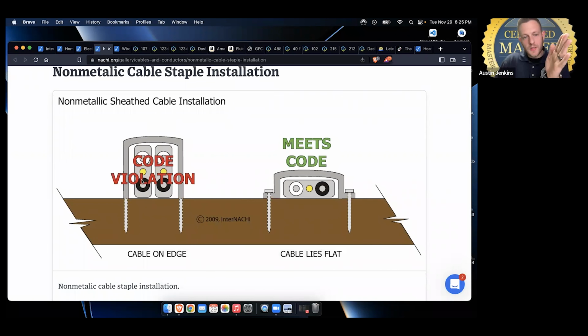So you've got the two conductors in a vertical pattern with the ground in the middle, which is actually a code violation per the National Electric Code. Most of the time, however, due to the way the staples are made, the wires will sit flat and flush with the finished surface, and that's okay.